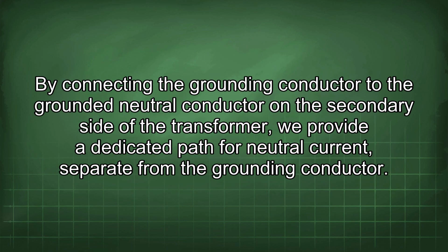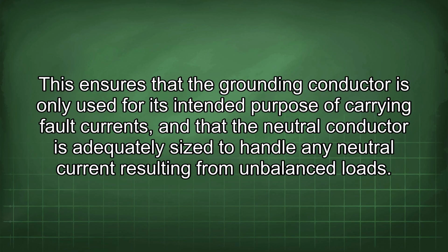By connecting the grounding conductor to the grounded neutral conductor on the secondary side of the transformer, we provide a dedicated path for neutral current separate from the grounding conductor. This ensures that the grounding conductor is only used for its intended purpose of carrying fault currents, and that the neutral conductor is adequately sized to handle any neutral current resulting from unbalanced loads.